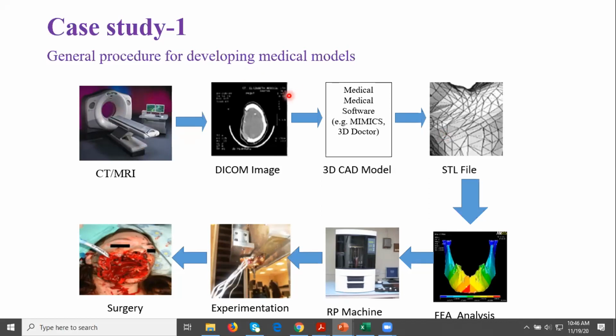When I want good results, I use higher energy and get accurate dimensions, but the radiation dose to the patient increases. The medical community does not accept that. So we have to reduce the radiation dose and improve the accuracy of the CT image. That is required when manufacturing a patient-specific implant.